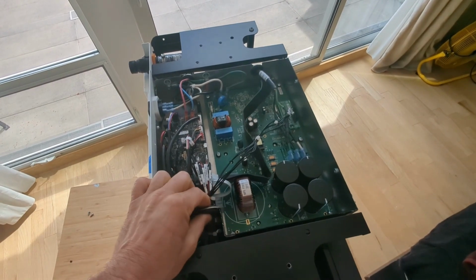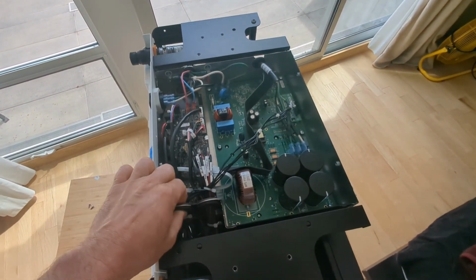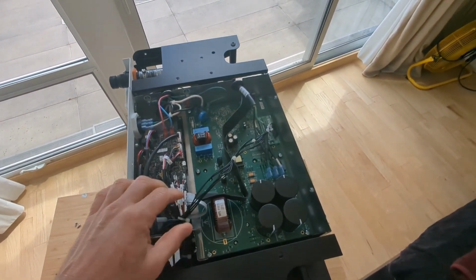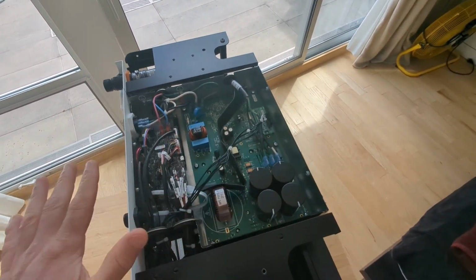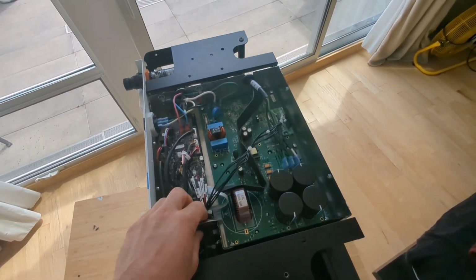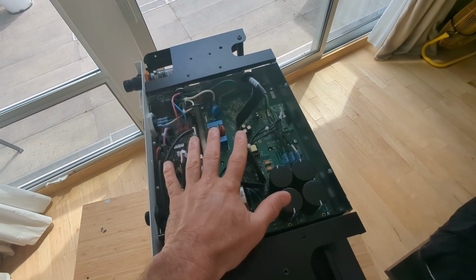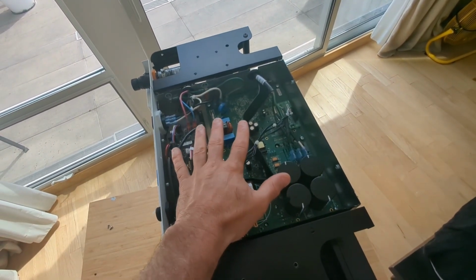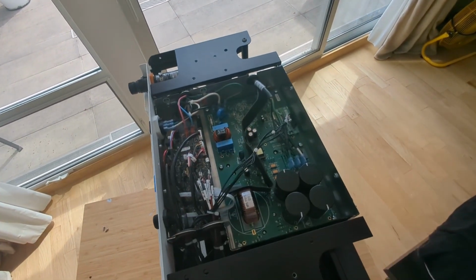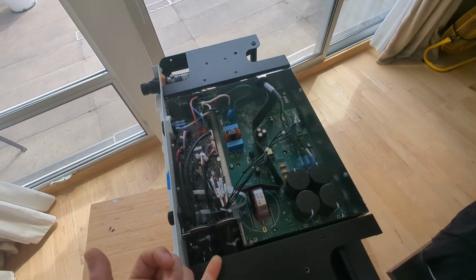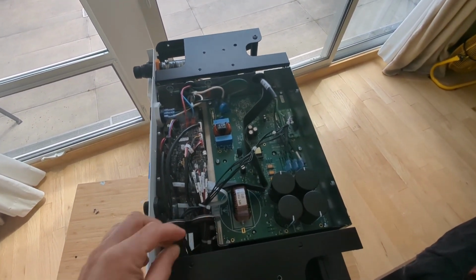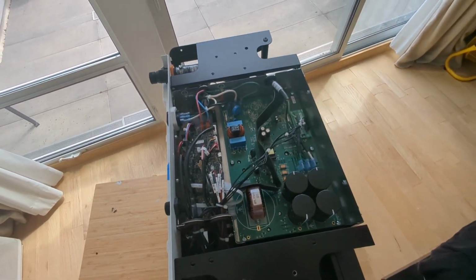It would have been better to fill this with some kind of foam or something just to keep them from getting in. You don't want to hermetically seal this box unless you're going to fill it with nitrogen, because then you'll have problems with condensation and pressure equalization between the inside of the box and the outside of the box as temperature changes. But you can put something in there to try and block the insects from getting in.